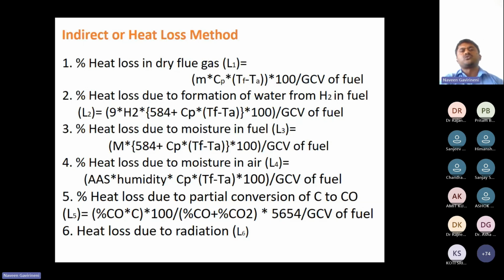Here are the percentage heat loss to dry flue gas, heat loss due to formation of water from H2 in fuel, loss due to moisture in fuel, moisture in air, and heat loss due to partial combustion of C to CO. So the fourth and fifth points are not coming. As per the BEE and the Indian Ministry of Power, we have considered this also.